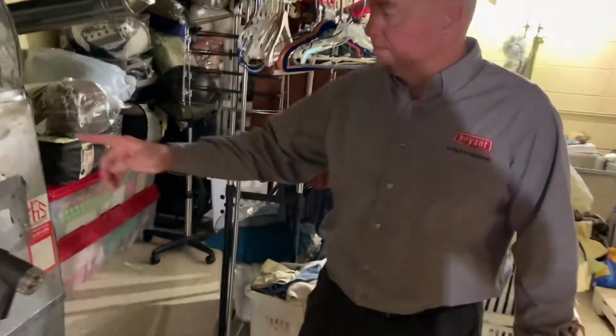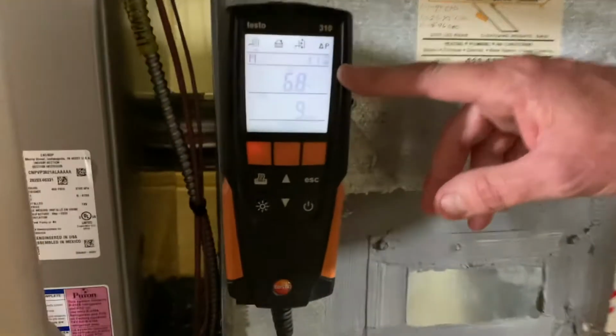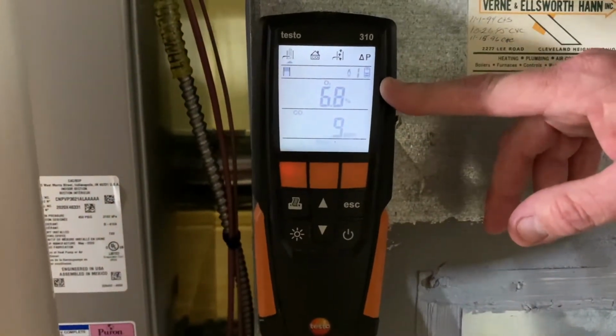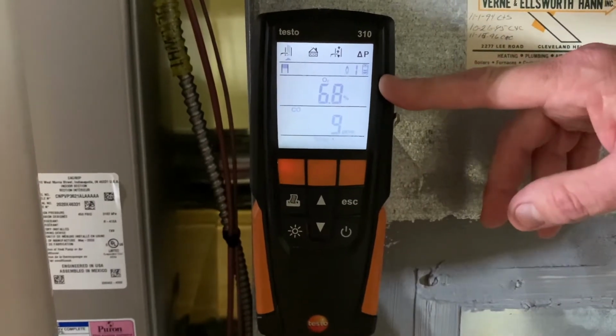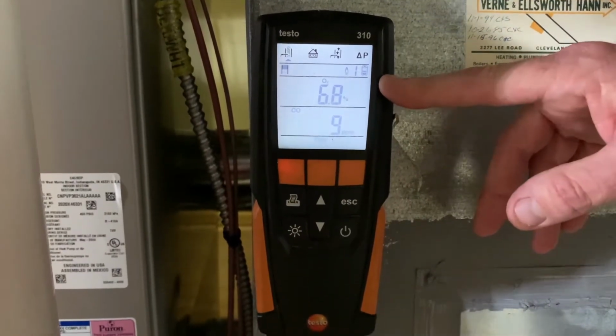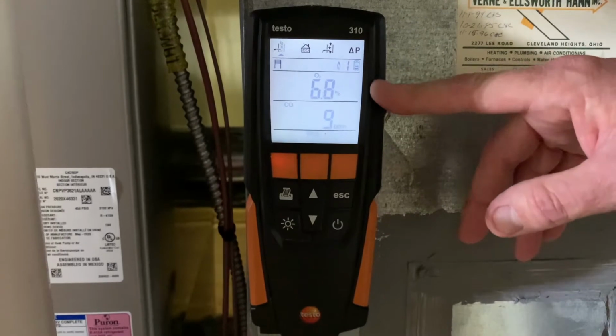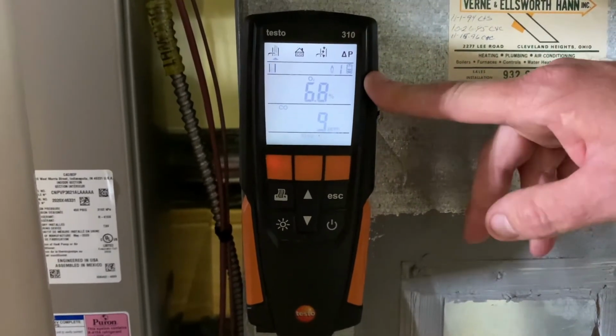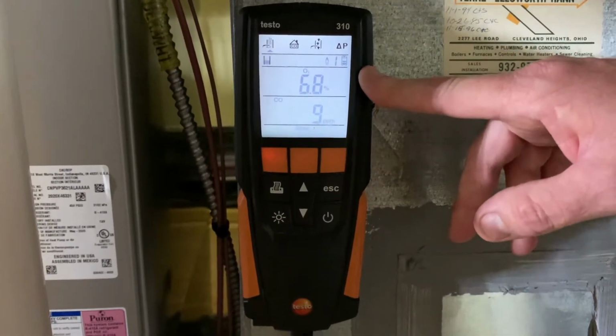It looks like this. You'll see this appliance has been up and running for about 10, 15 minutes now. We're running about 6.8% O2, which is a great number. I tell guys, anything above 5, that number should be very stable. It shouldn't be bouncing around. It shouldn't be going down.